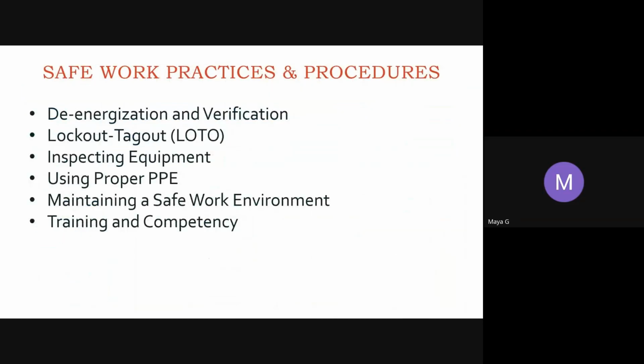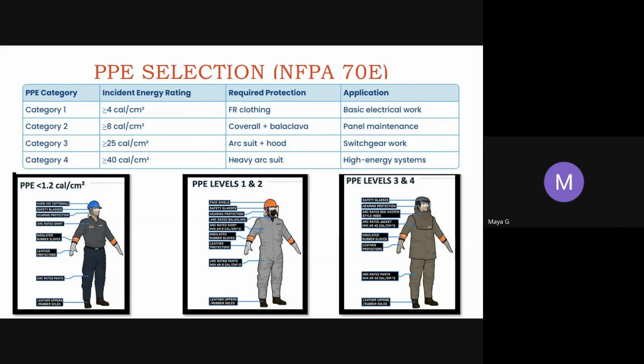We have already dealt with the first three. We'll deal with the PPE. There are 4 categories of PPE based on the incident energy rating, and the suits are shown here. The category of PPE is selected according to the incident energy rating. For high energy systems, we use the highest category, category 4, which covers incident energy of more than 40 calories per square centimeter. It will protect the worker from a heavy arc.